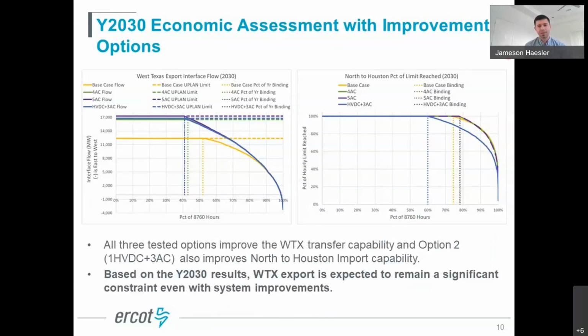Diving into the results a little bit, but not getting too deep in the weeds here: these two graphs are flow duration curves of the West Texas export interface on the left, and what we call the north to Houston interface on the right, which is basically a primary import path from the north into Houston. These curves show what percentage of the year the interface is binding at its limit, with our base case in yellow, and then how the tested improvement options perform relative to that base case. The first thing to note is that all three options do improve the West Texas export capability and lessen the percent of the year that interface is binding.